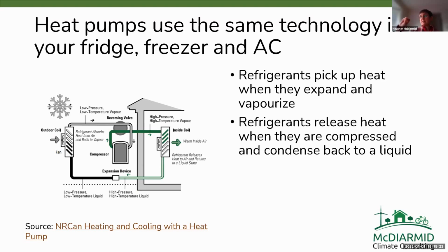It highlights how we've got this cycle where we're moving refrigerant between the outside box, the heat pump, and the inside air exchanger or air handler. The refrigerant picks up heat outside in the wintertime as it expands and vaporizes. If you want to boil water, converting it from liquid to gas requires adding heat—the water absorbs that heat as it moves from liquid to gas. With a refrigerant, it's picking up heat from the outside as it expands and vaporizes. Then you move that vaporized refrigerant inside, compress it, and force it back to its liquid state, where it gives up the heat it picked up earlier. That's how you're able to move heat from one place to another.